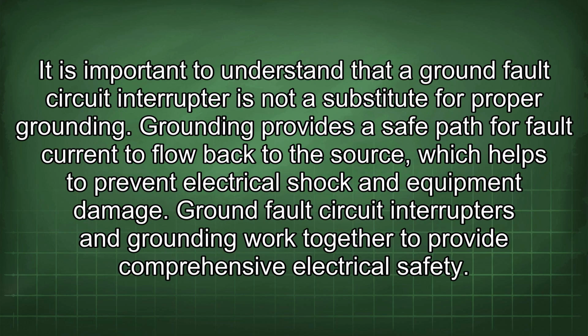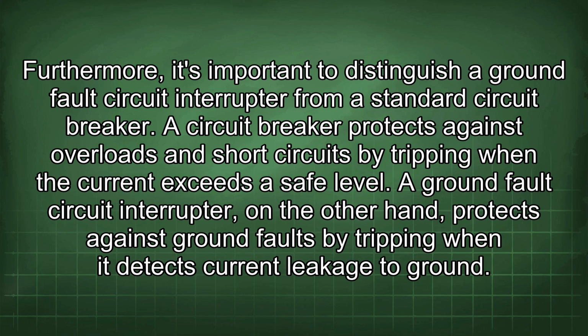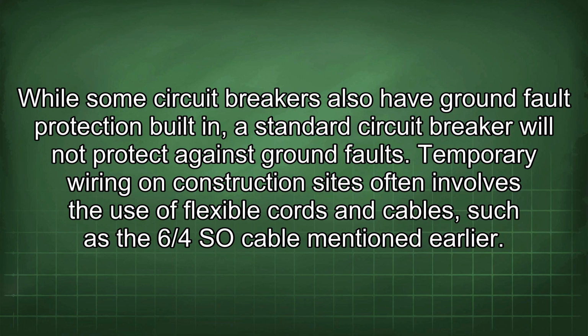It is important to understand that a ground fault circuit interrupter is not a substitute for proper grounding. Grounding provides a safe path for fault current to flow back to the source, which helps to prevent electrical shock and equipment damage. Ground fault circuit interrupters and grounding work together to provide comprehensive electrical safety. Furthermore, it's important to distinguish a ground fault circuit interrupter from a standard circuit breaker. A circuit breaker protects against overloads and short circuits by tripping when the current exceeds a safe level. A ground fault circuit interrupter, on the other hand, protects against ground faults by tripping when it detects current leakage to ground. While some circuit breakers also have ground fault protection built in, a standard circuit breaker will not protect against ground faults.